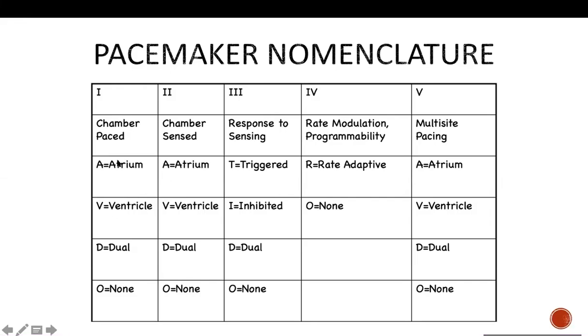So for example, if your atrium is okay, you're waiting for the atrial beat to kick in before you pace the ventricle. So you have to sense the atrium, and if you sense the atrium, you might want to trigger the ventricle. But if there is an intrinsic ventricular beat, you're going to inhibit the ventricle. So there are a little bit of tangles over here, because you're looking at the atrium and the ventricle in both ways, whether to trigger or inhibit depending on intrinsic activity or not. That's what the device does. It senses both, paces both, and inhibits and triggers depending on which signal is there.